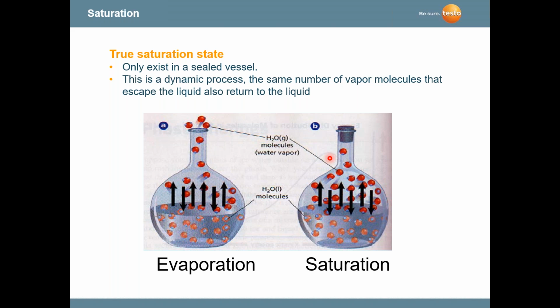We consider the term evaporation when we're boiling water because the liquid is escaping out of the device, whereas in an air conditioning system, we shouldn't have anything escaping. If we do, we obviously have a refrigerant leak, and that needs to be corrected. But in saturation, we're adding heat, and the molecules are changing from a liquid to a vapor.